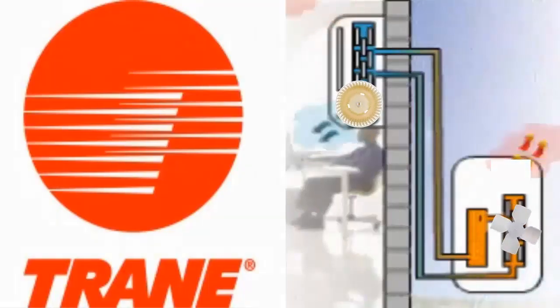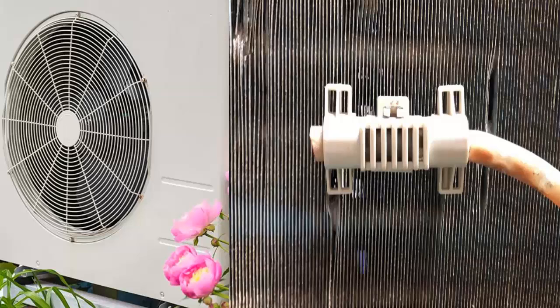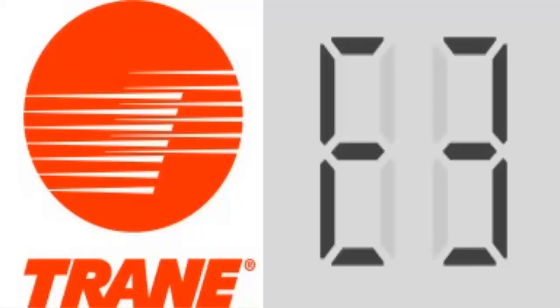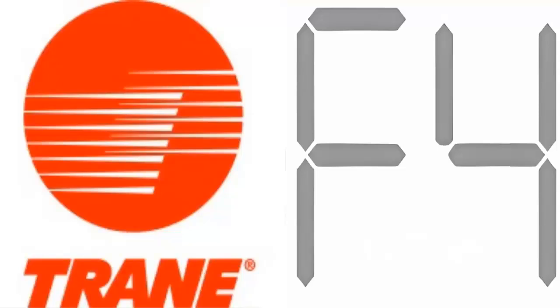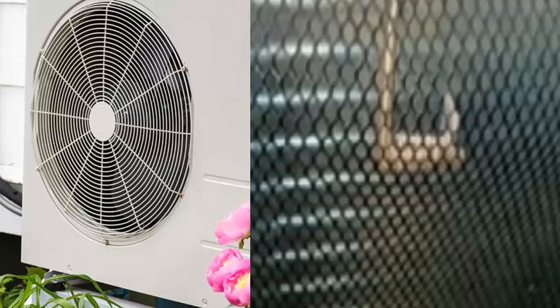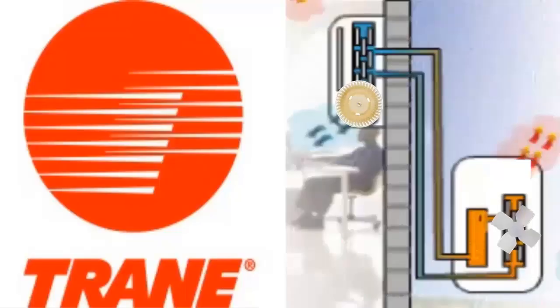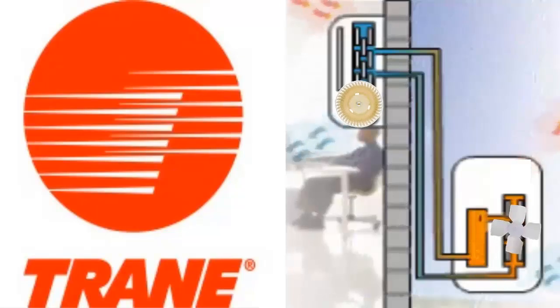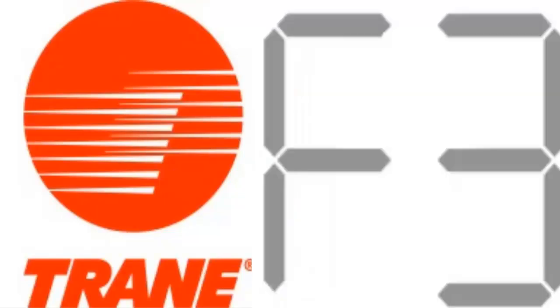3. When there are issues with the temperature sensor located in the outdoor unit, which measures the temperature of the outdoor unit's heat exchanger, codes E3, F4, and P8 can be generated. 4. When there are issues with the temperature sensor located in the outdoor unit, which measures the temperature of the outdoor air passing through the unit's heat exchanger, codes E7, F3, and P8 can be generated.